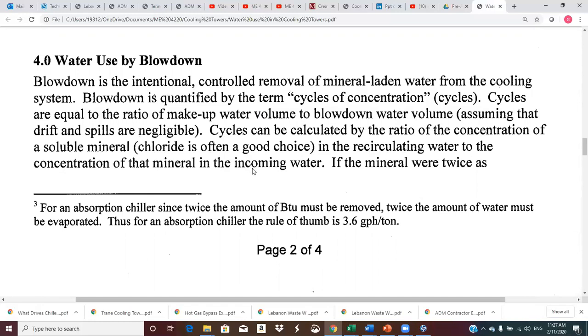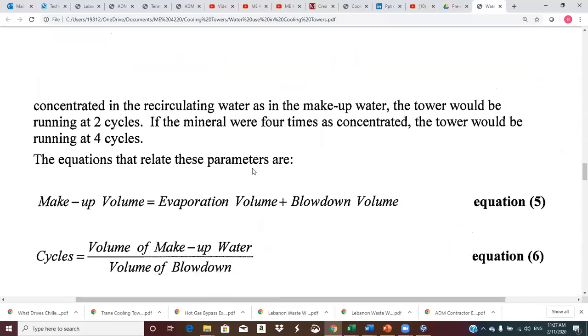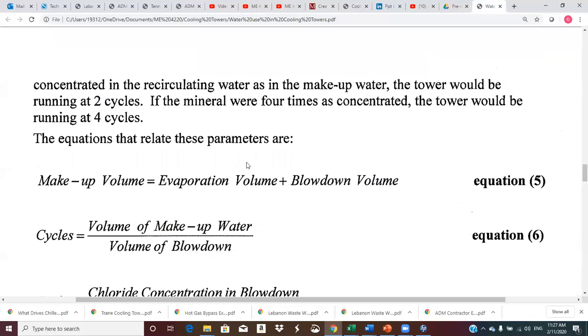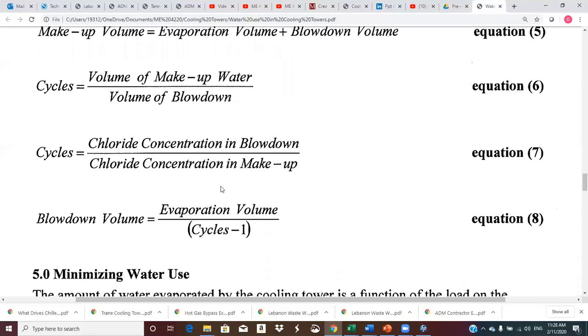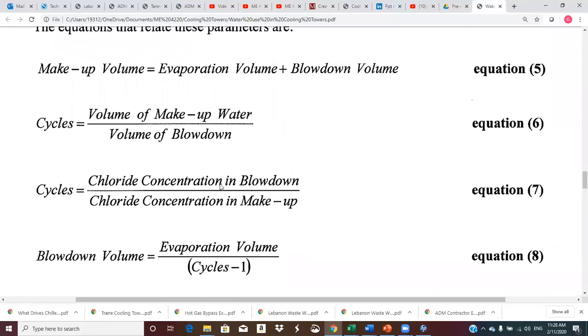So if the mineral was twice as concentrated in the recirculating water as the makeup water, the tower would be running at 2 cycles of concentration. If the mineral were 4 times as concentrated, the tower would be running at 4 cycles. So here are some equations all summarized together. The makeup water is the evaporated water plus the blowdown, and in that we've included any other losses from the tower. They're just grouped in there together.